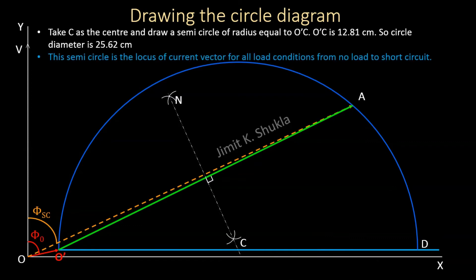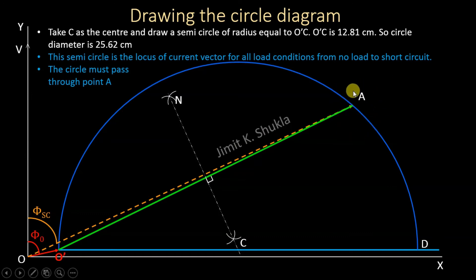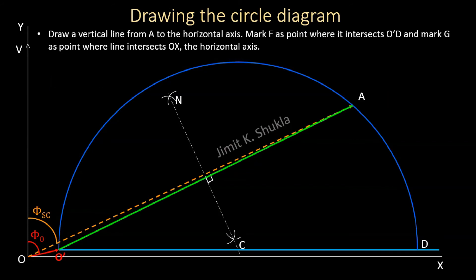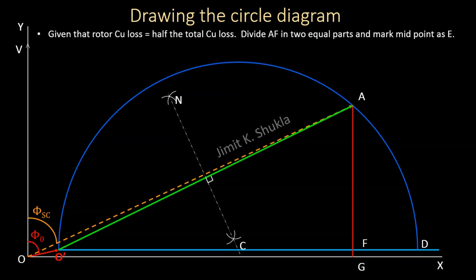This semicircle is the locus of the current vector for all load conditions from no load to short circuit for the induction motor. We must verify that the circle passes through point A. If it does not, there is a measurement or drawing error. We then draw a vertical line from A to the horizontal axis, marking point F where it intersects O'D and point G where it meets horizontal axis OX.